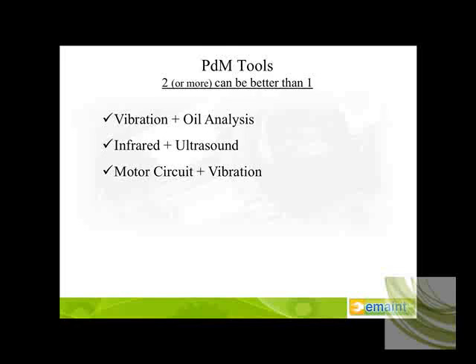Thermography, infrared, cannot see corona. Ultrasound can hear corona, particularly on a high humidity day where your infrared camera is going to have issues seeing problems in the upper insulators or connectors in an open air high voltage substation.